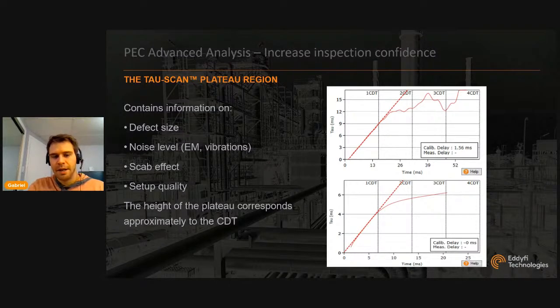You'll get information on noise. If there is electromagnetic noise or vibration, this is a good case here with significant noise affecting the tau scan calibration curve. Scab effect is also going to affect this region, the setup quality. If you see the tau scan, especially the calibration tau scan, end before 3CDT, that means that the A-scan window is too short. That would happen typically if you do your smart pulse and then recalibrate on existing areas with a thicker wall thickness, then you'll see that tau scan calibration get under 3CDT. Typically, we recommend recalibrating, redoing a smart pulse in those cases. You want your tau scan to last between 3 and 4 CDT, especially for the calibration.